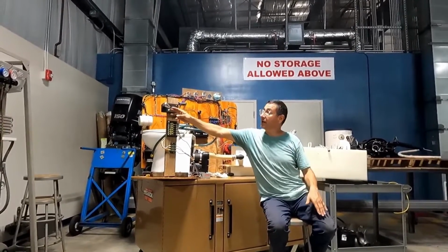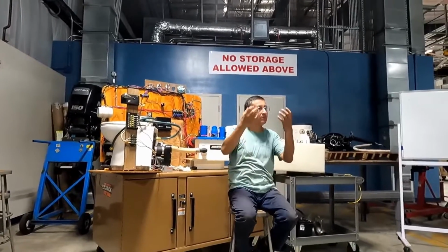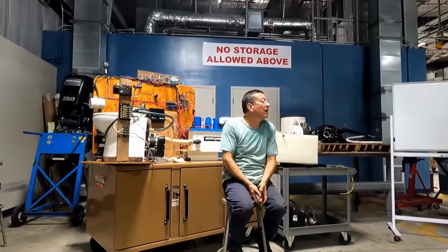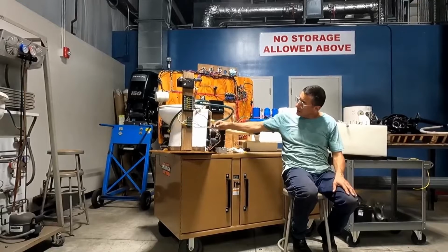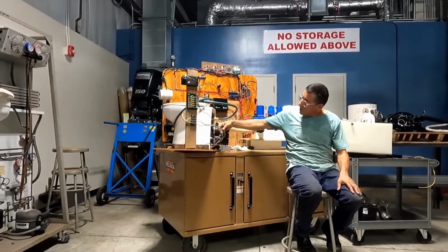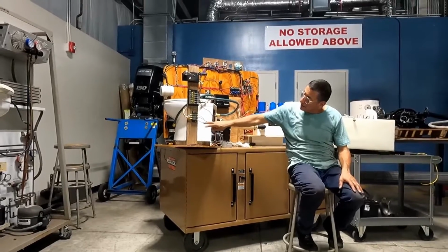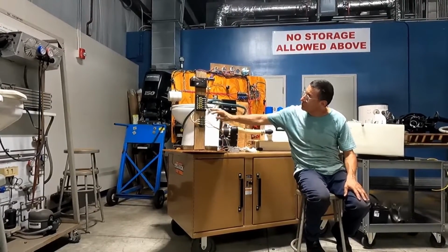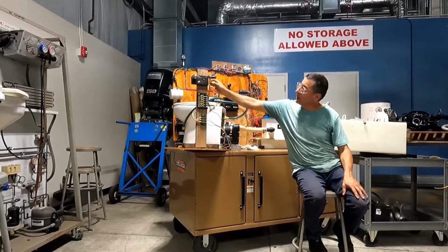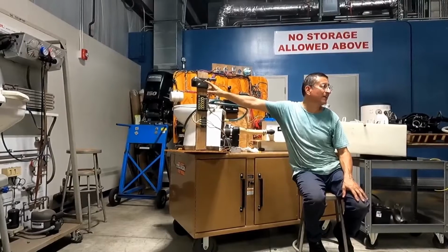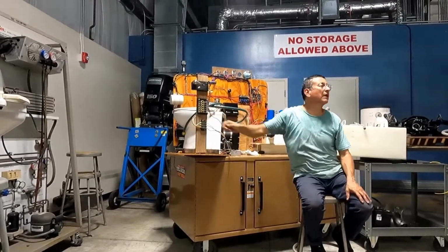Okay, and the second one, you activate what? The pump and suction, negative pressure. And you have those four cables. Look at this, it's a black, white, yellow, blue, and red. Those three cables, yellow, blue, and white, are for the solenoids here. The red is for the positive bus bar and the black for the negative bus bar.